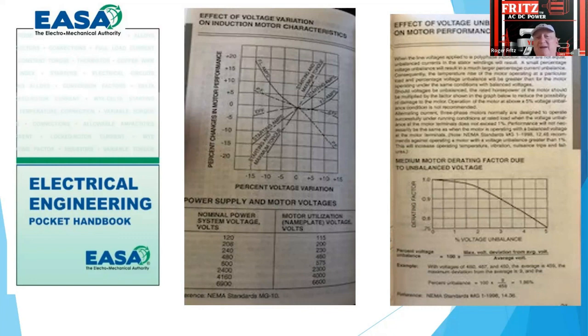We also utilize the technology to make three-phase power instead of using a single-phase motor when you only have single-phase power. You've got two power lines there, but we can convert it to DC, and with proper sizing of a 3-phase inverter, and also single-phase input inverters, we can build through 3-phase. The 3-phase motors are much more efficient than single-phase. On average, a single-phase motor is about 70% efficiency, maybe 72%, and a 3-phase is up in the 90s. So just changing a single-phase circuit out with an inverter, you do have a 3% loss in the inverter, but your total control saves a lot of power.